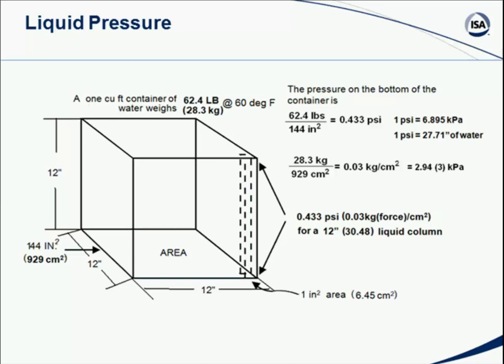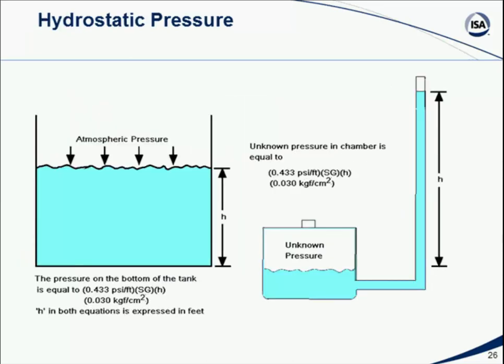That's an important number because we use it in a lot of cases for calculating the level in tanks. Of course, if we're in Europe, we use a slightly different unit. We're going to be talking about 0.03 kilograms of force per square centimeter, but there are conversions that go back and forth. But that's the basic principle: the column of fluid presses down on a given surface area, and if we can measure that pressure, we can determine the height of the column. In fact, we've been using that concept for years.